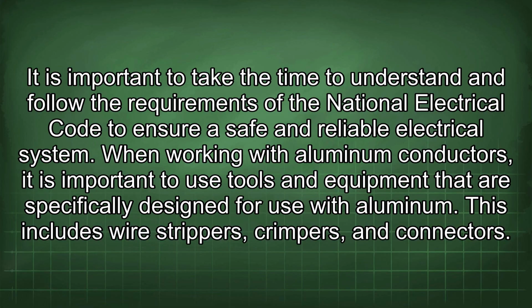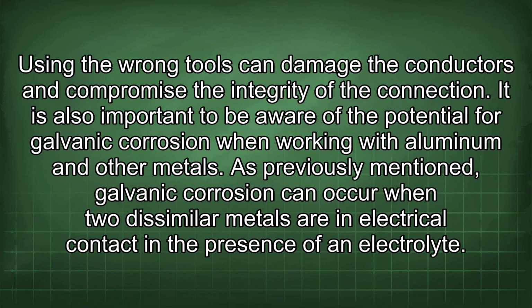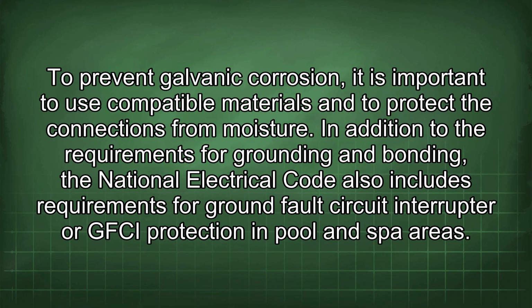When working with aluminum conductors, it is important to use tools and equipment that are specifically designed for use with aluminum. This includes wire strippers, crimpers, and connectors. Using the wrong tools can damage the conductors and compromise the integrity of the connection. It is also important to be aware of the potential for galvanic corrosion when working with aluminum and other metals. As previously mentioned, galvanic corrosion can occur when two dissimilar metals are in electrical contact in the presence of an electrolyte. To prevent galvanic corrosion, it is important to use compatible materials and to protect the connections from moisture.